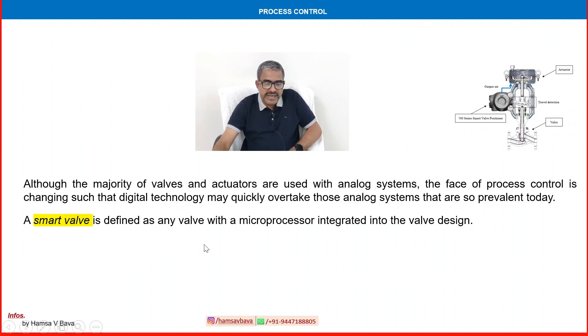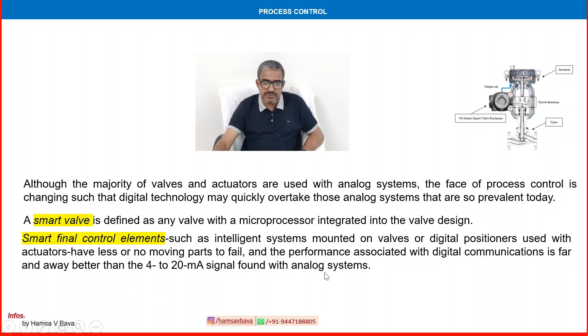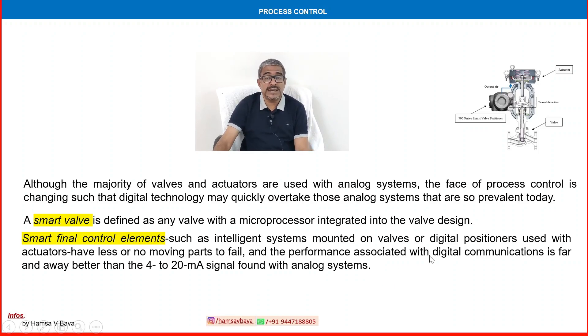A smart valve is defined as any valve with a microprocessor integrated into the valve design. Smart final control elements such as intelligent systems mounted on valves or digital positioners used with actuators have fewer or no moving parts to fail, and the performance associated with digital communication is far better than the 4 to 20 milliamp signal found in analog systems. Performance is much, much better than the old analog system.